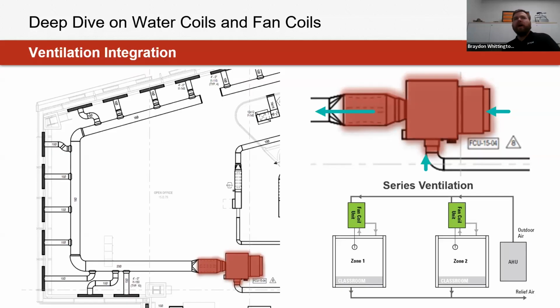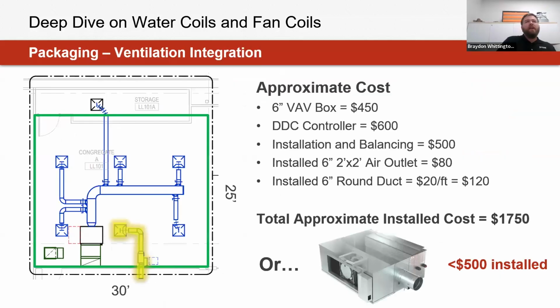But here's just an example there too of just a series ventilation system where essentially now you have a blower coil that's serving a long line of diffusers by the perimeter, but then also bringing in your ventilation through that fresh air intake, also paired with this product as well. Benefit of that being for some of the ventilation integration is it's cutting down on some of the additional cost that would be required for adding an additional single duct within this system. So additional ductwork that would need to be considered there too. Separate outlet conditions that you might have to lay out as well, a form of controller that we're pairing, and just making sure that those mesh well with the existing equipment within this system.